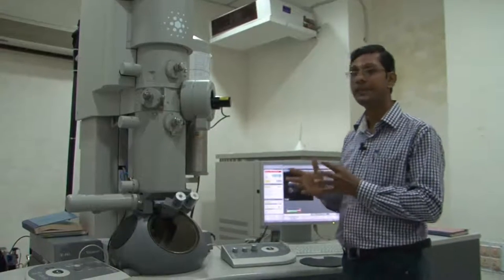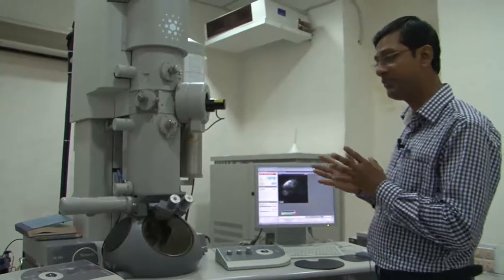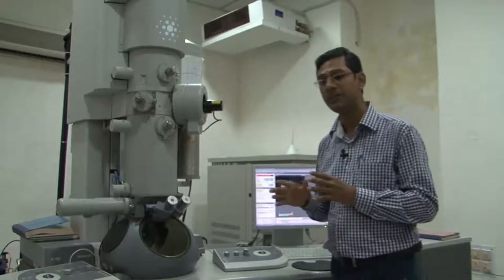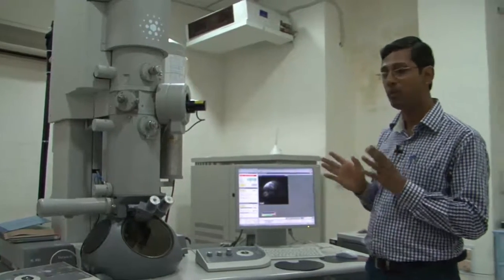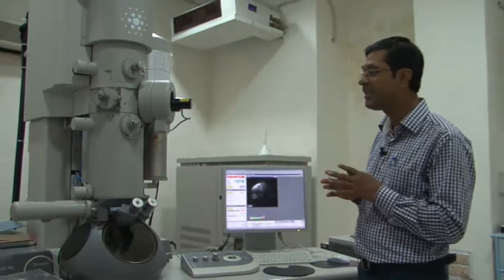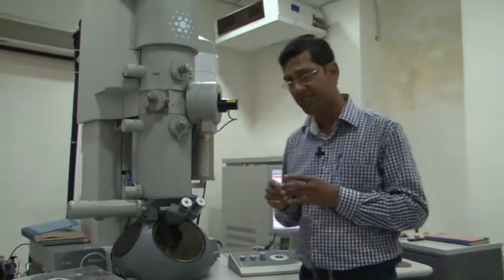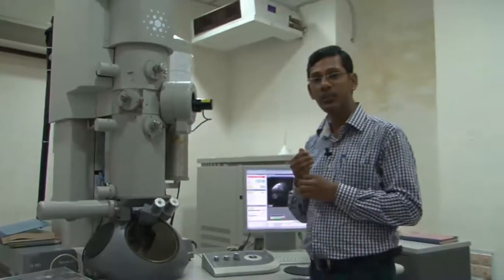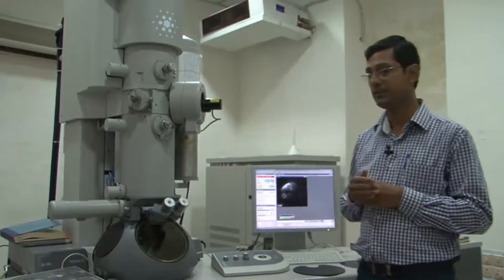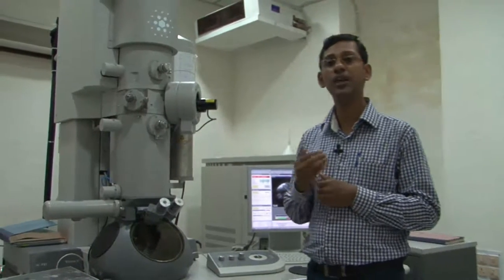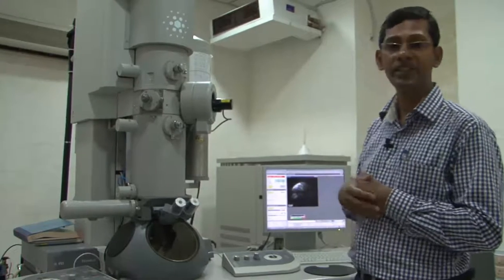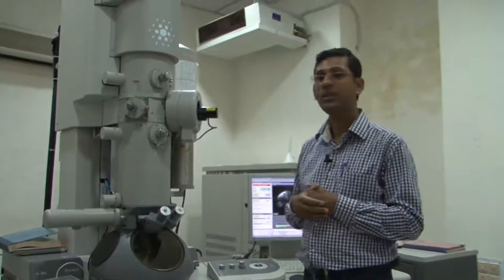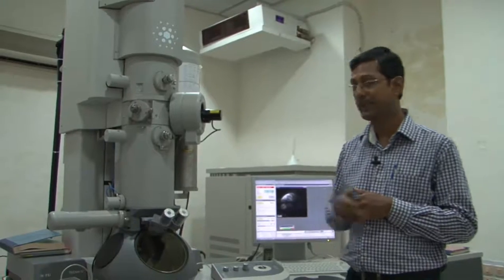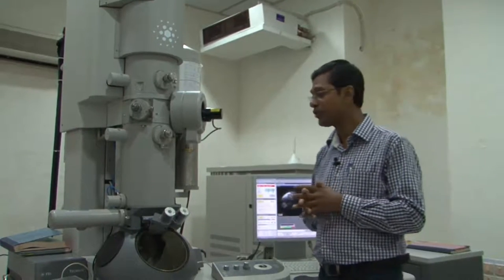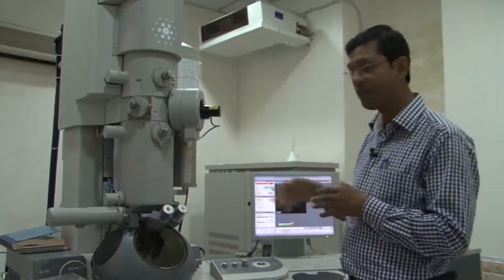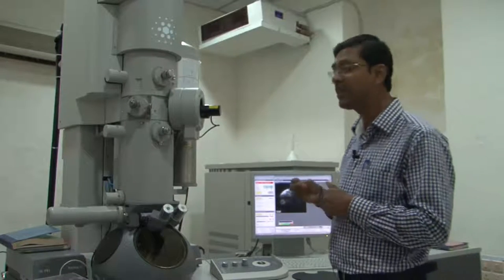Other than that, the microscope needs to be kept in a very neat environment, free from any kind of vibration, free from any kind of magnetic field, and also free from noise. Probably we will see sometime down the line, if I have the opportunity, I will show a microscope with the best possible resolution called Titan, which will be installed at IIT Kanpur.